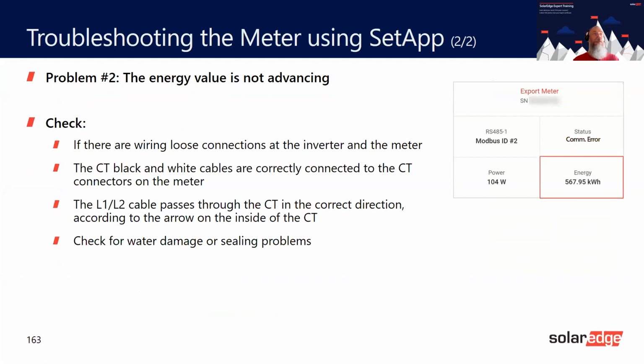Problem number 2, the energy value is not advancing. So this is the energy value here. You want to check the ID, you want to check the COM. We've got errors here with communication, and we've got value here. And it says if there's wiring loose connections, the inverter or meter, just to check that. Check that the CT black and white cables are correctly installed in the right place. And check that L1 and L2 cable passes through the CT in the correct direction. So the CTs are both facing to the grid. And again, check for any water damage or sealing problems.